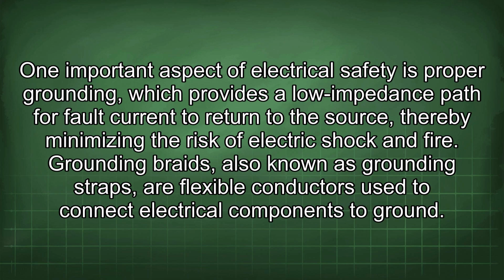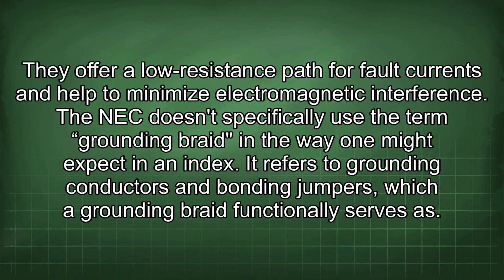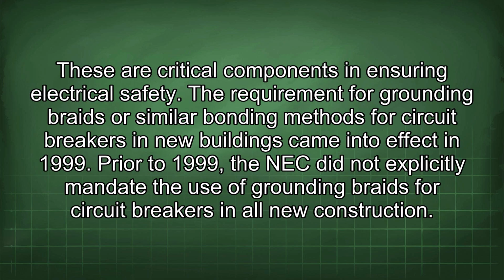Grounding braids, also known as grounding straps, are flexible conductors used to connect electrical components to ground. They offer a low resistance path for fault currents and help to minimize electromagnetic interference. The NEC doesn't specifically use the term grounding braid in the way one might expect in an index. It refers to grounding conductors and bonding jumpers, which a grounding braid functionally serves as. These are critical components in ensuring electrical safety.